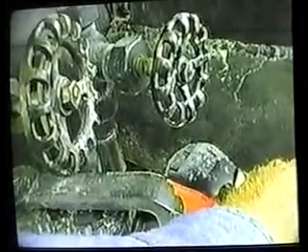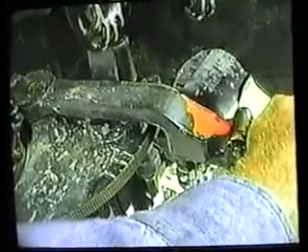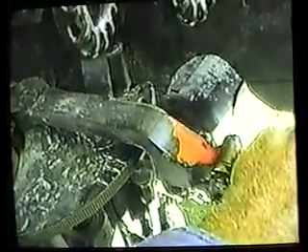Now, you want to avoid a heavy explosion when the oil ignites, using only enough oil to generate steam without making black smoke. It's important that the atomizer be opened first, then open the firing valve gradually. Now, once you've got a fire going, you can bring it up to the first notch here. This is where you'd want the firing valve to be until you've got a nice warm boiler.